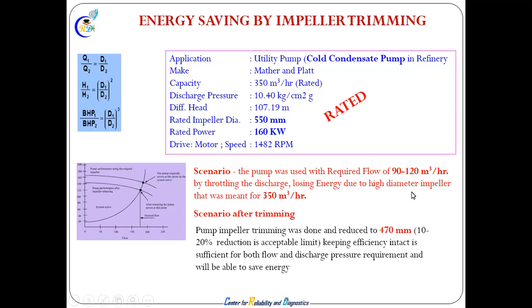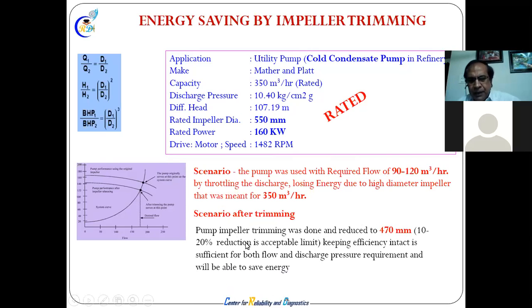So see, they want to go from 350 cubic meter per hour to around 100 cubic meter per hour. They have done trimming from 550 to 470. You cannot trim as much as you want in an impeller, otherwise the entire function and geometry will be lost, and it will create a problem for the formula. Without going deep, the normal understanding is that you cannot go more than 10 to 20% reduction of the diameter. So that is taken care of. They have taken around a 15% reduction in the impeller diameter.